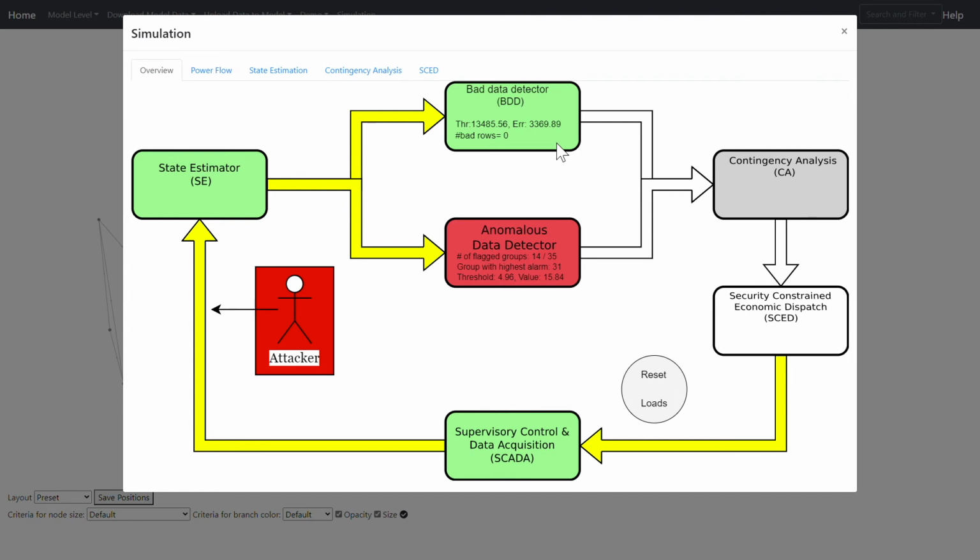But for now, let's just see what would happen on a normal EMS, which doesn't detect the attack. And so what would happen, we just simply again run RTCA on the false measurements, which again would show that nothing is wrong, because what the attack is doing is basically to modify or change slightly the value of some of the loads, but it still represents a realistic and a normal state. So now if we run SCOPF, the system will redispatch some generation to reflect the changes in loads and to get back to the most economical operating point.